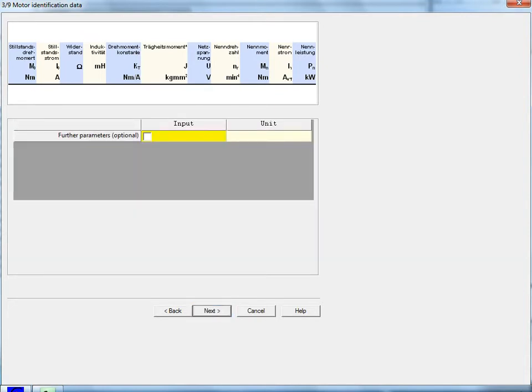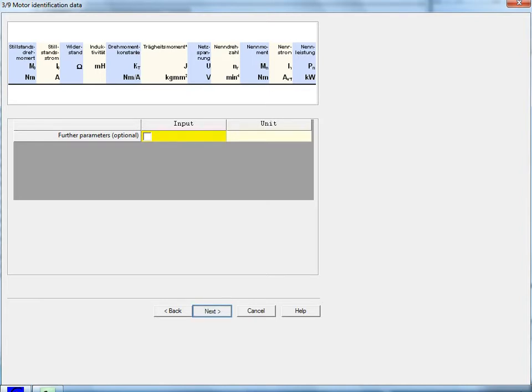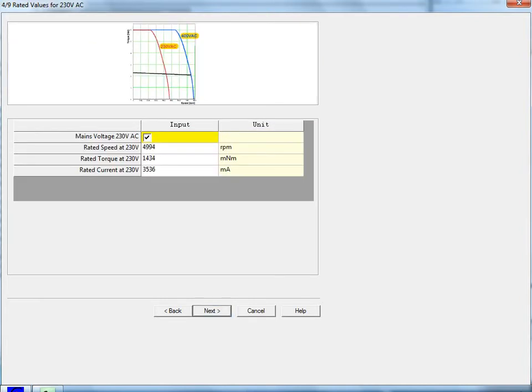Step 3 allows an optional maximum DC voltage. Thus, if the motor is rated for 160 volt DC, like an SM231AE, but the drive can take 230 volts AC, this would prevent a user from enabling the drive with 230 volts AC connected and damaging the motor. This would cause a 3210 DC link voltage exceeds limit error. This motor is a standard winding, which can take 230 volts AC, so I'm not going to change that.